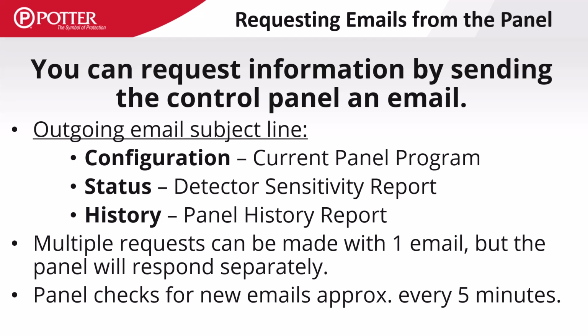Requests for the control panel to respond with information can be sent via an email. The panel will only respond to email requests from an authorized recipient who has been enabled using the panel programming software. The items that can be obtained from an email request are the panel history report, a detector status report, or the panel's configuration program. These items are requested using 3 keywords sent in the subject line of the email.